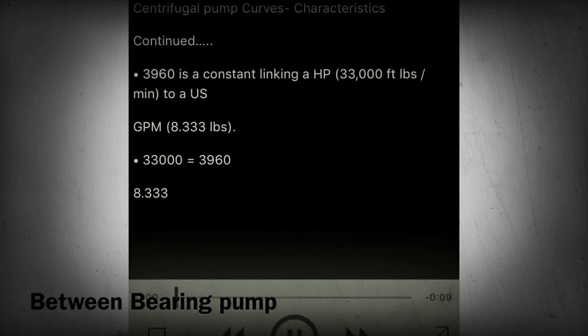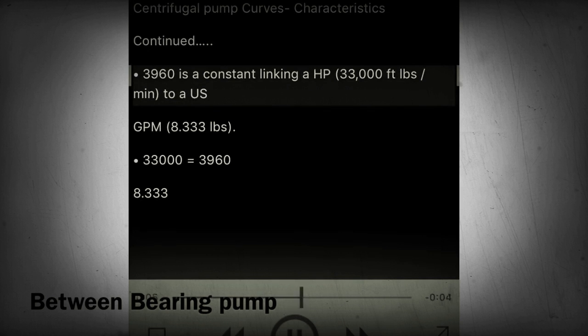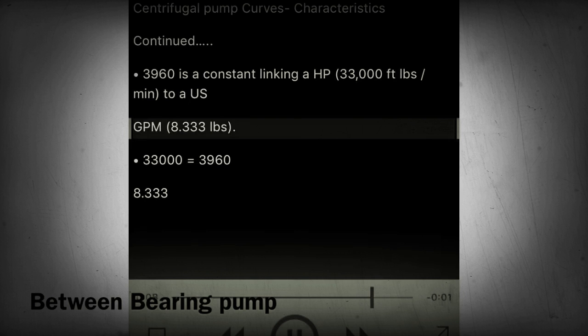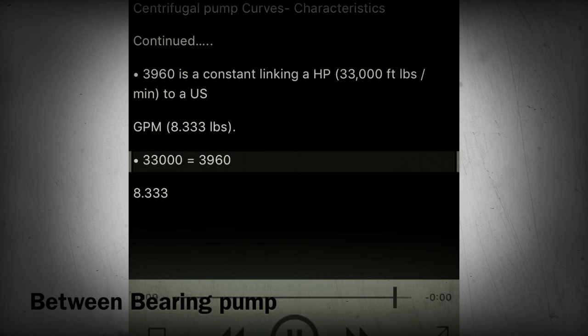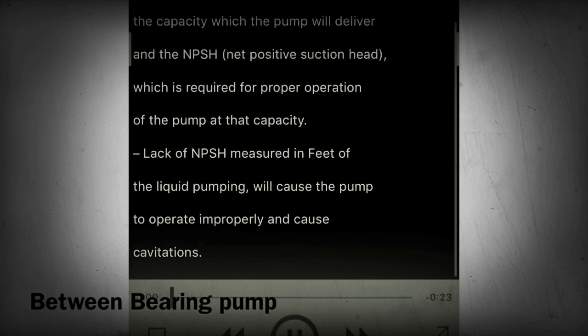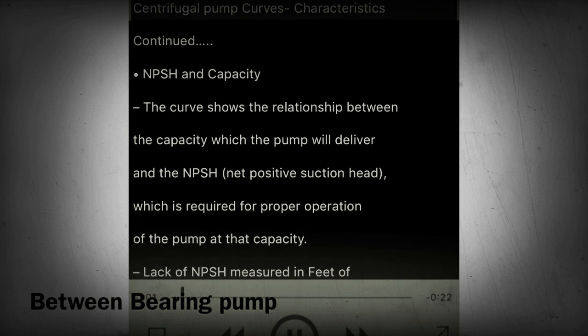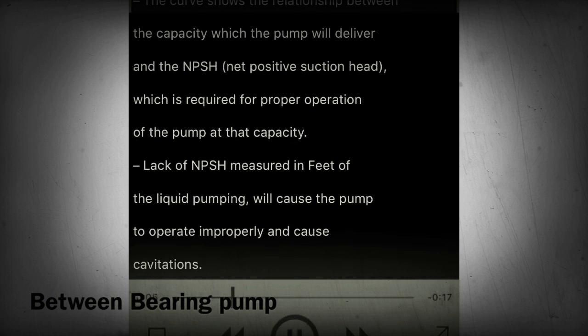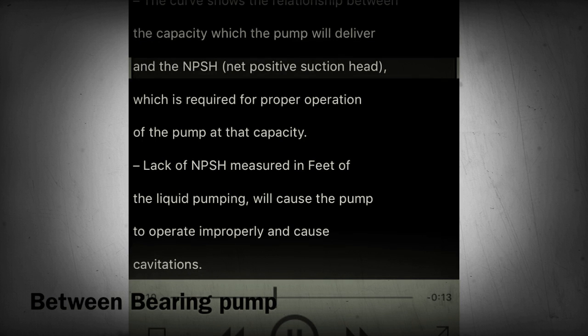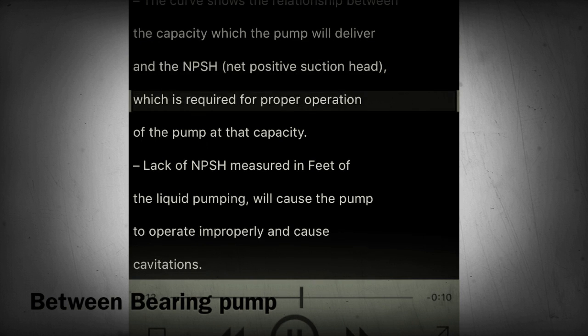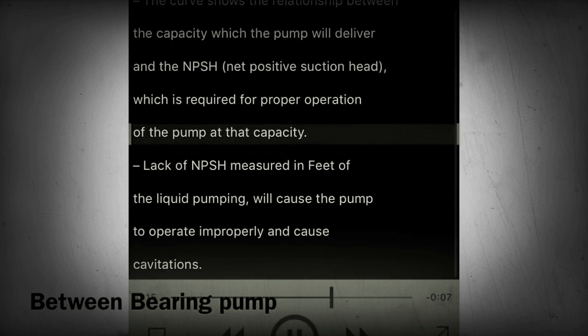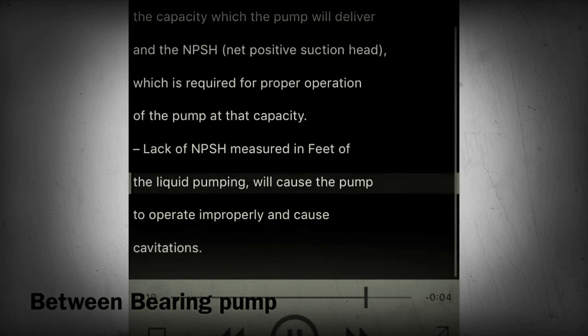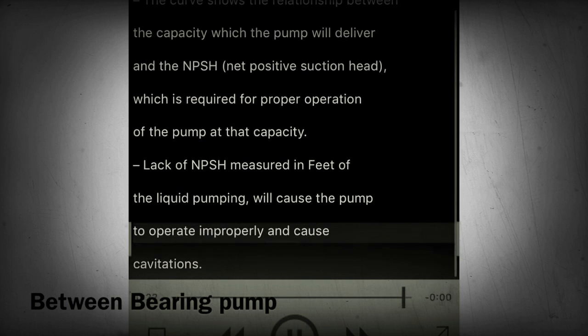Section 25 - The constant 3,960 links HP (33,000 ft-lbs/min) to US GPM (8.333 lbs), since 33,000 ÷ 8.333 = 3,960. Section 26 - NPSH and capacity: the curve shows the relationship between the capacity the pump will deliver and the NPSH (net positive suction head) required for proper operation of the pump at that capacity. Lack of NPSH, measured in feet of the liquid being pumped, will cause the pump to operate improperly and cause cavitation.